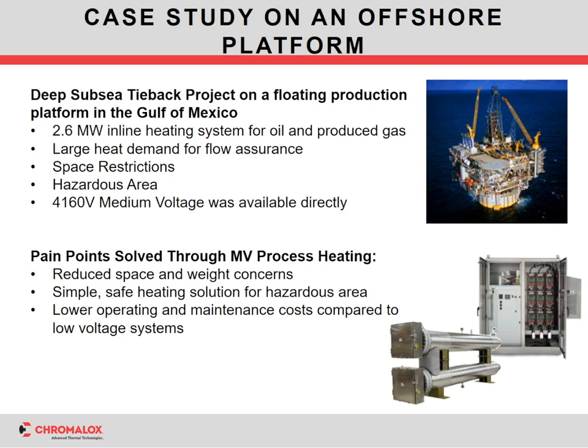And again, as you know, on an offshore platform, there are space restrictions. It was a hazardous area, but medium voltage was ideal for this case, as the power generation on the platform itself was at 4,160, which is typical for a lot of generating, so it lent itself to medium voltage. But beyond simply the hazardous location, which we're used to, the reduced space and the weight concerns were actually the number one priority for the customer.